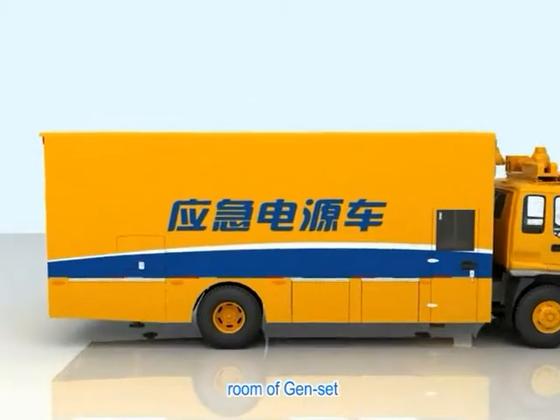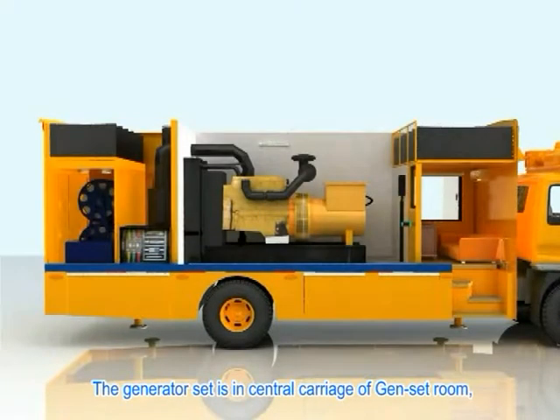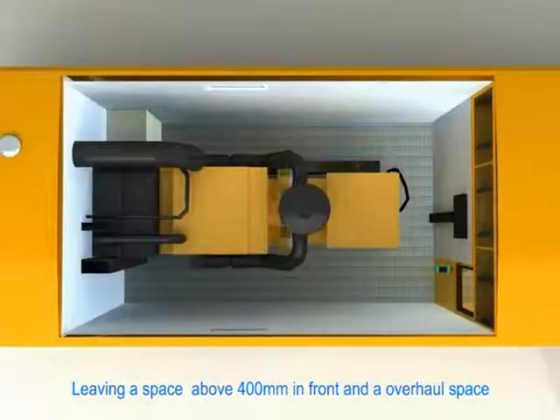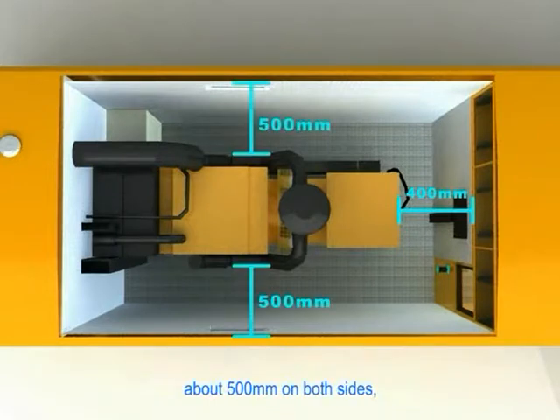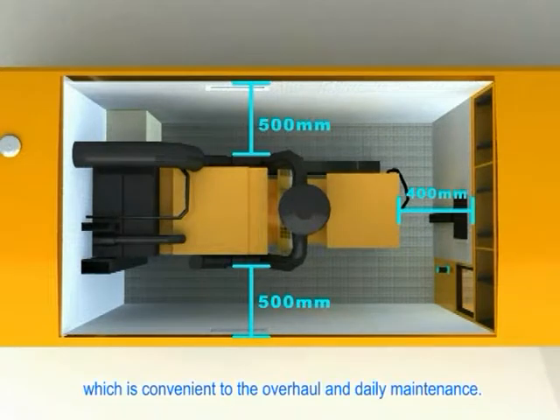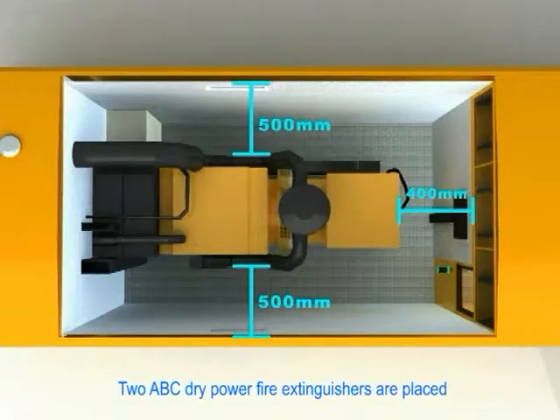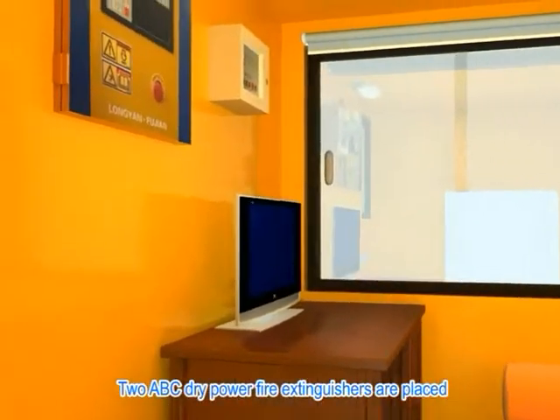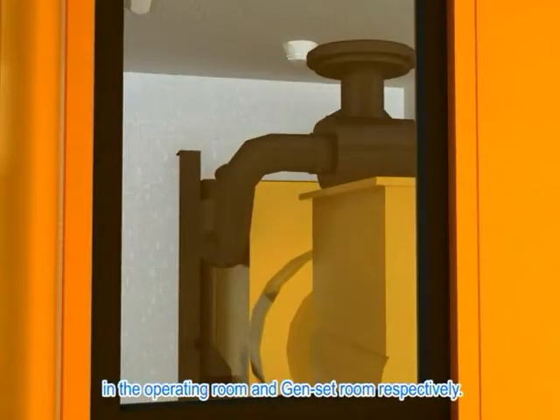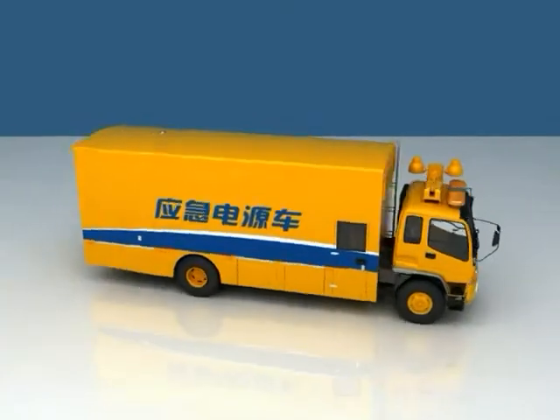Room of gen set. The generator set is in the central carriage of the gen set room, leaving a space of about 400 mm in front, and overhaul space of about 500 mm on both sides, which is convenient for overhaul and daily maintenance. Two ABC dry powder fire extinguishers are placed in the operating room and gen set room respectively.